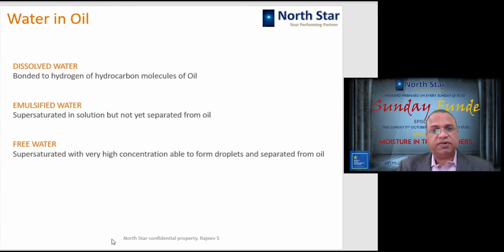Then there is emulsified water, when there is a high saturation of moisture in the oil. So some amount of moisture gets supersaturated, and it is not yet fully separated from the oil. So it is not fully absorbed into the oil and not fully separated from the oil. So it is in this emulsified condition.